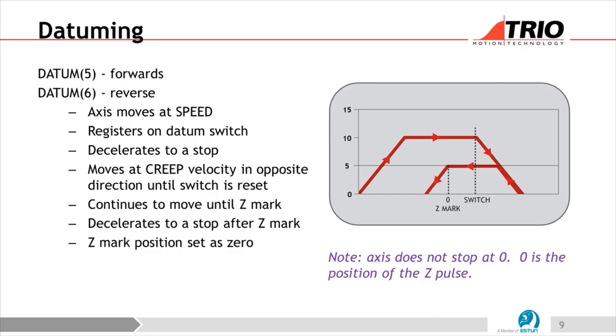If you use only the switch in that position, the switch has some variation in position, based on the weather, the situation, the lifetime of the switch. So the homing position can differ over time, or suddenly after power off and power on. Then you have to calibrate again. Exactly. So there is an offset, which is not good for precise applications. So the combination of the switch and Z mark gives you the exact position always, because the Z mark is always the same position.